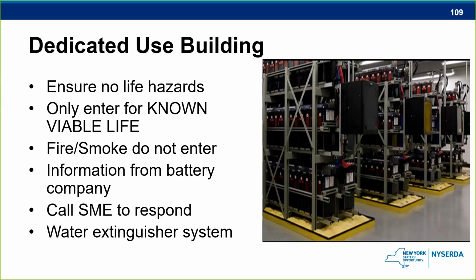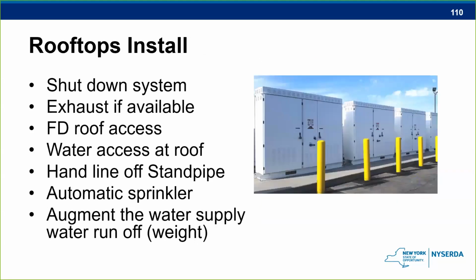Right? This is where that large-scale testing comes in. If the large-scale testing says you need to have a 0.3 or 0.5 gallons per minute per square foot, then that's what you need to have for the installation. So don't be afraid to ask. So when you go over a certain threshold, that large-scale testing has to take place. And we didn't get deep into that 9540A, but that's a pretty good test to make sure that when these things go in, that they can be controlled if they go on fire. Next slide, please. All right, rooftop installations.